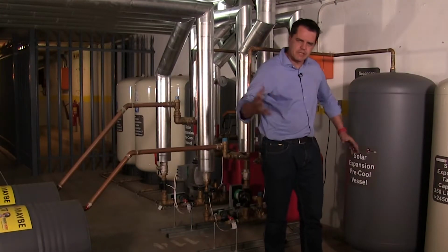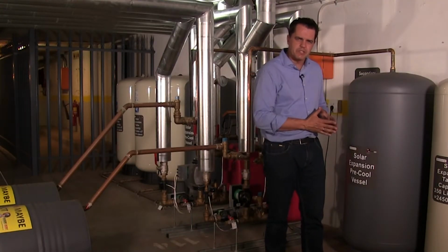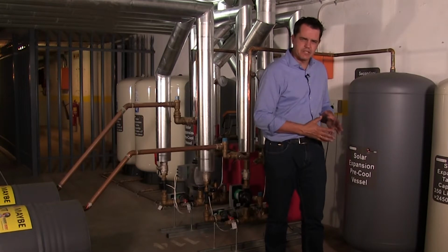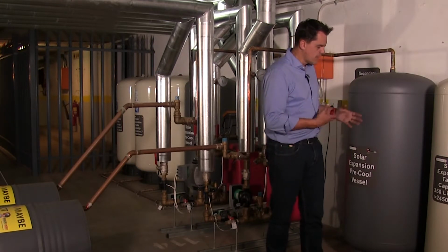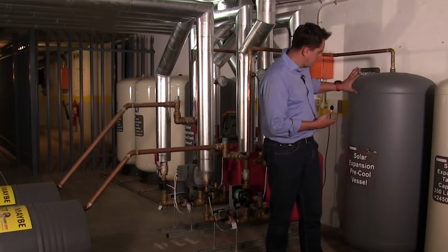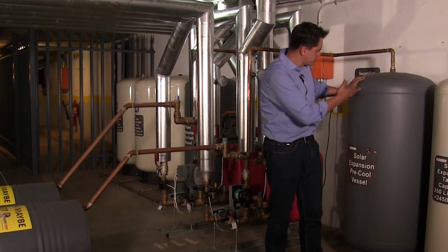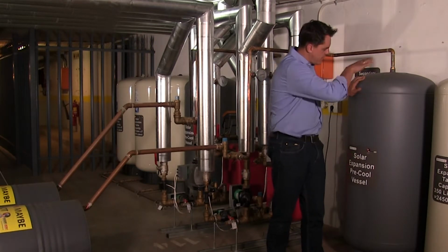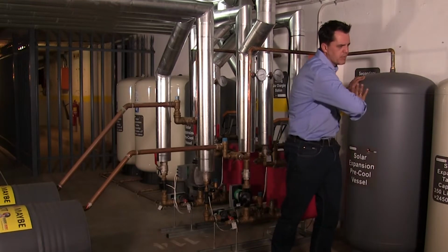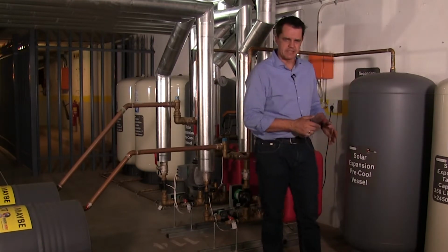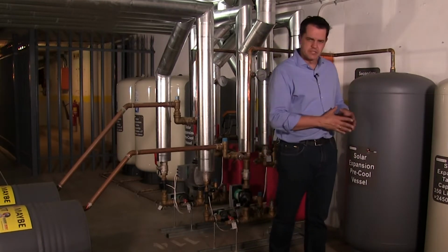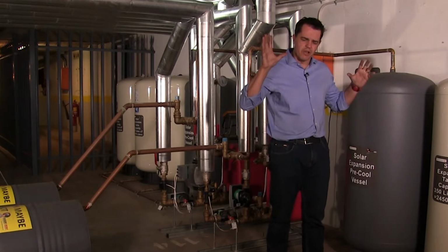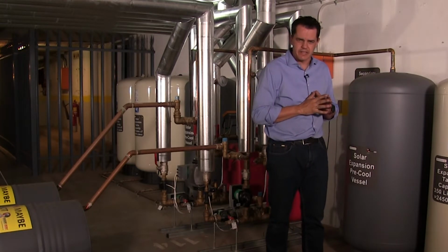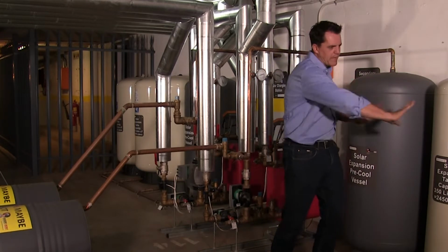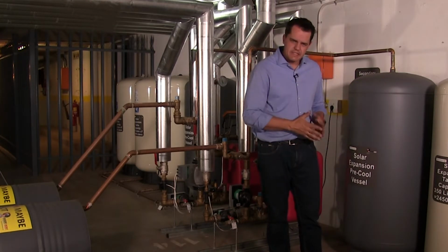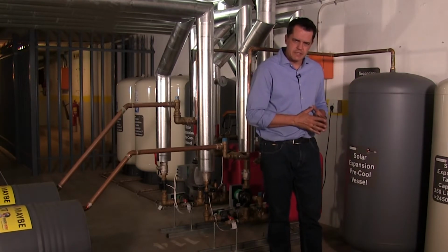If the system goes into stagnation, in other words, over temperature, so it's producing energy, but there's no consumption, the system goes into stagnation, it pushes this first tank, which is filled with cold water, it then expands this volume into these expansion tanks. And again, they're sized so that the entire liquid volume that's in the solar collectors on the roof can be expanded into these tanks. And hence, that's the way we protect the system.